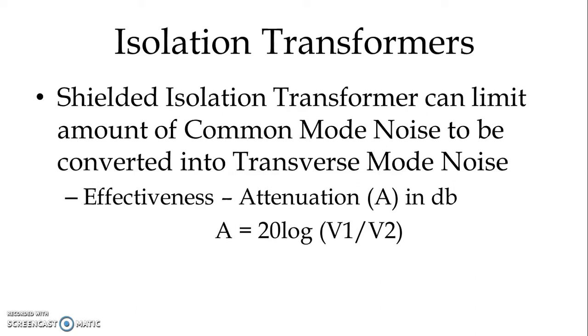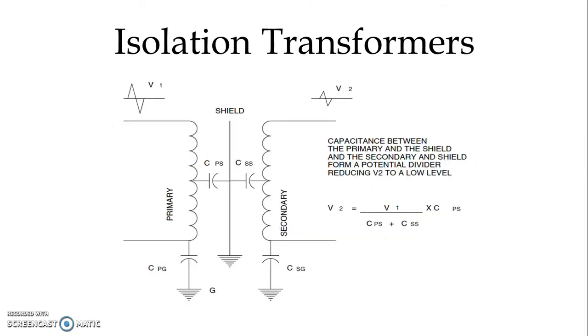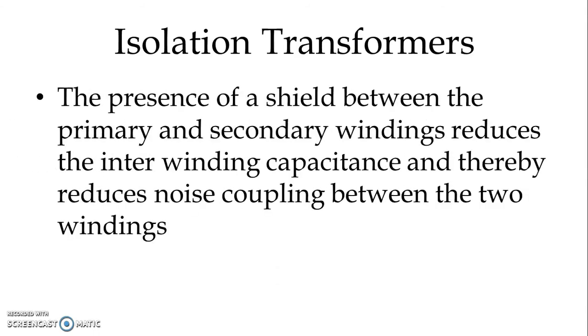We have one shielded isolation transformer which is used to attenuate the primary to secondary. The presence of shield between the primary and secondary winding reduces the interwinding capacitance and thereby reduces noise coupling between the two windings.